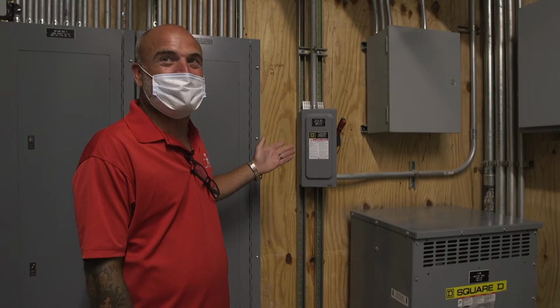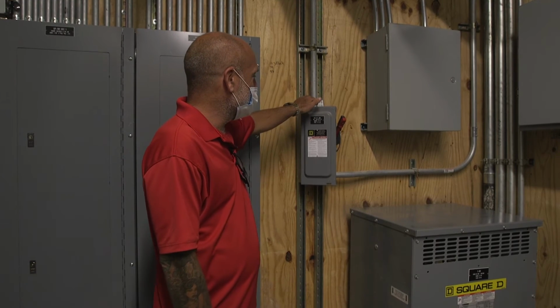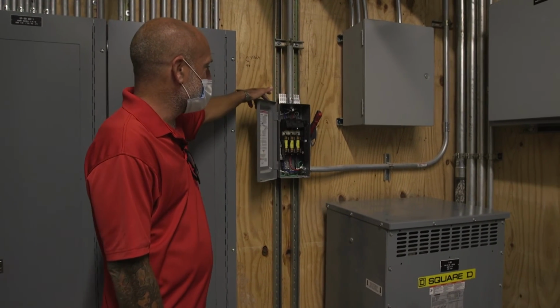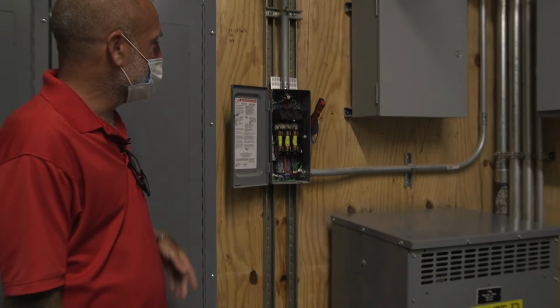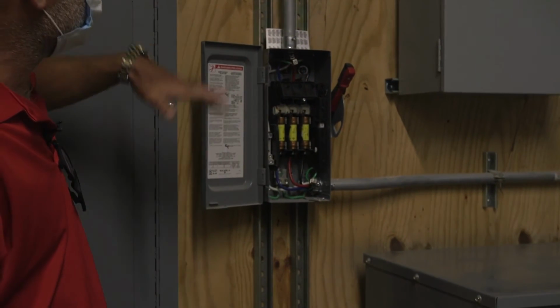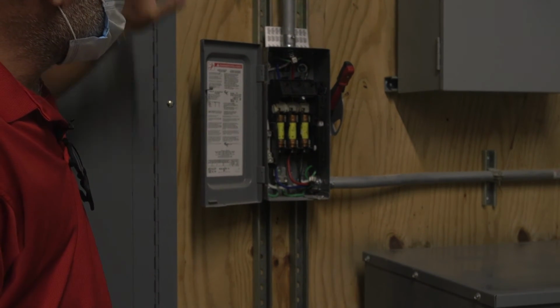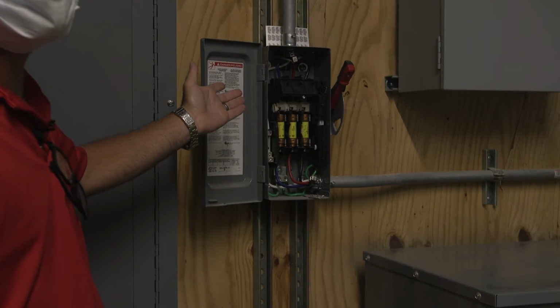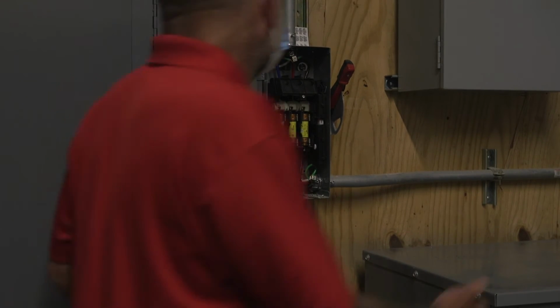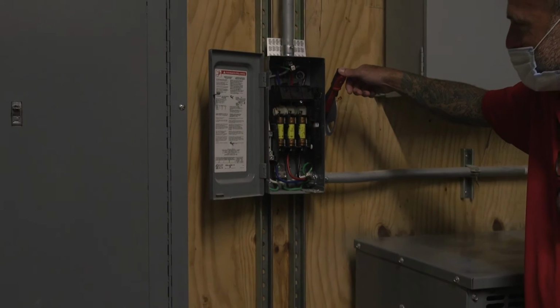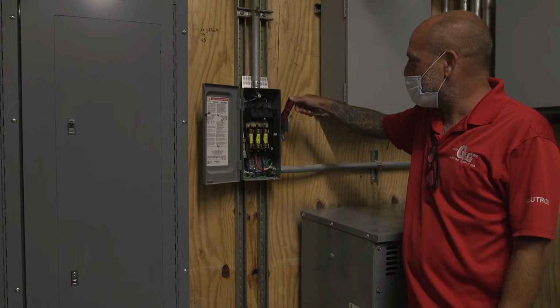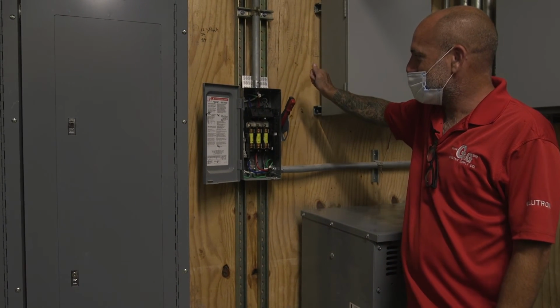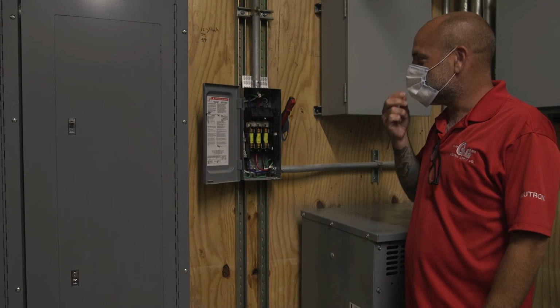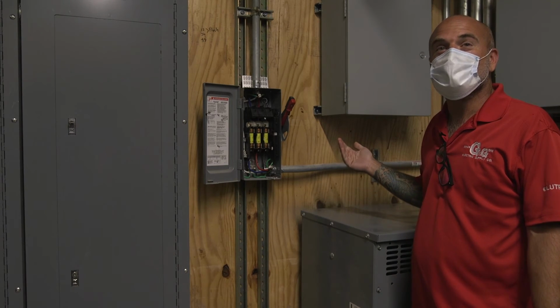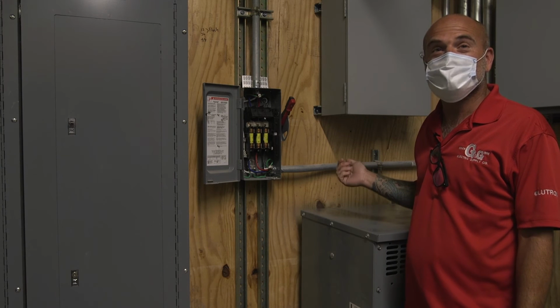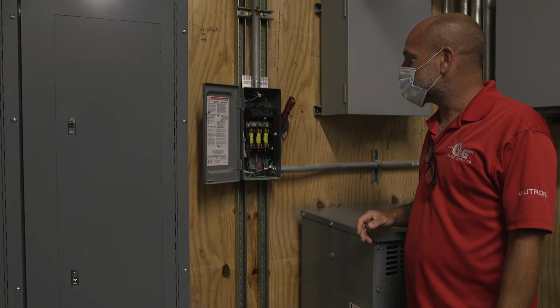This is a Square D safety switch. Basically, it's used to disconnect the load or protect the load moving forward by means of fuses. It can come in either fused or unfused. This is the handle that would turn it on and off. Down would be off, up would be on. Pretty much it's a maintenance-free thing. Probably maintenance should be done once a year. Turn it on and off just to keep it exercised.